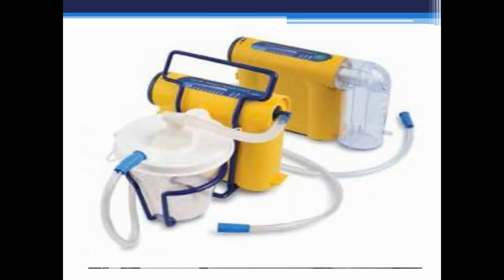Next, these are a couple of examples of the portable suction units. These are Laerdal LCSU4s. So very nice suction devices. They are portable, and oftentimes they'll have a little bit smaller canisters than you would see on a mounted suction unit. So if you're working an aggressive call, heavy amount of vomit and secretions, and these canisters are starting to fill up, what you can simply do is remove it, dump it on the ground, and then replace it.